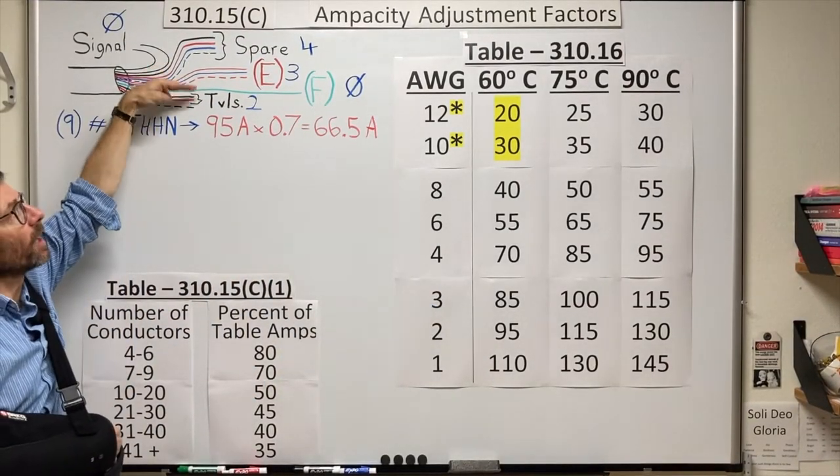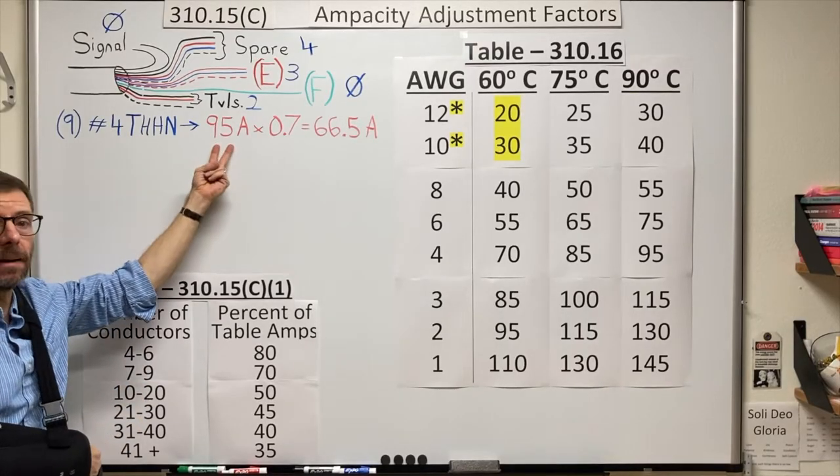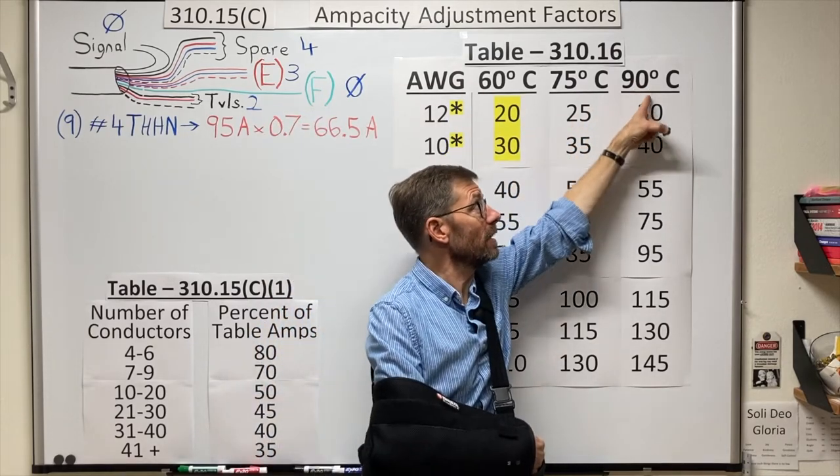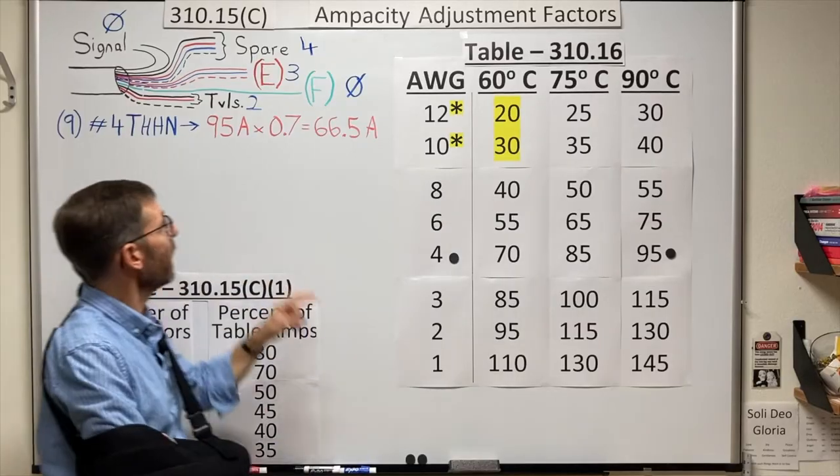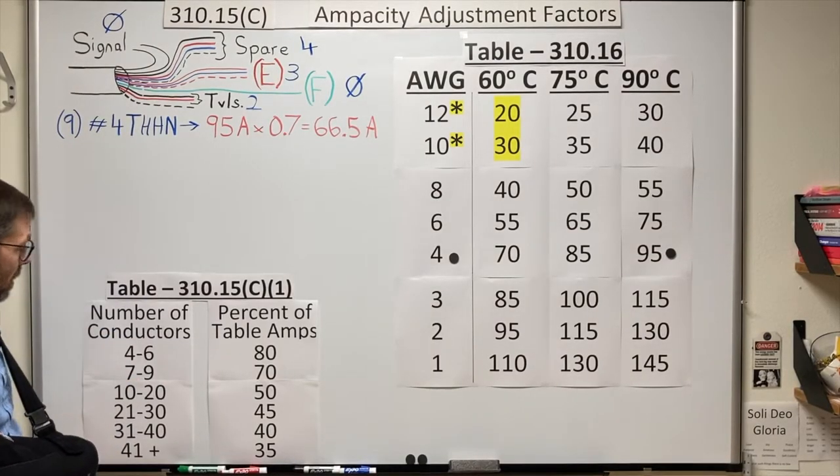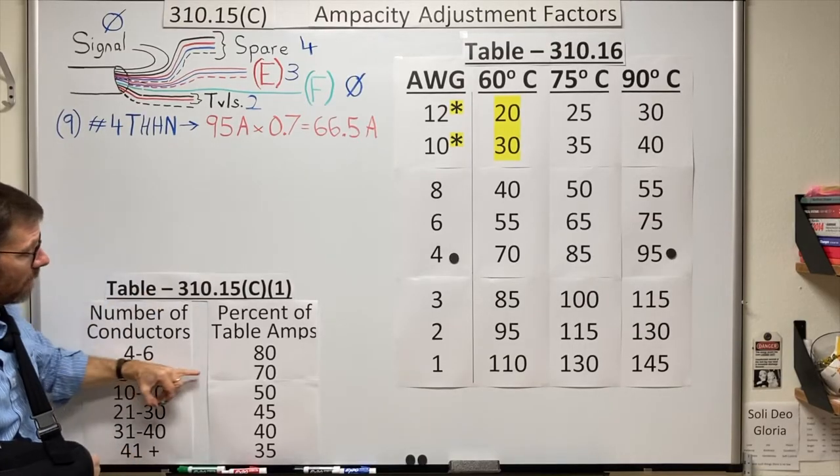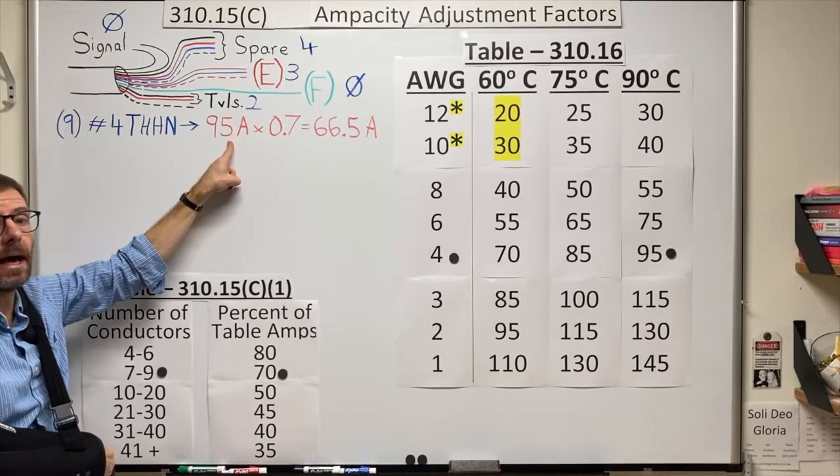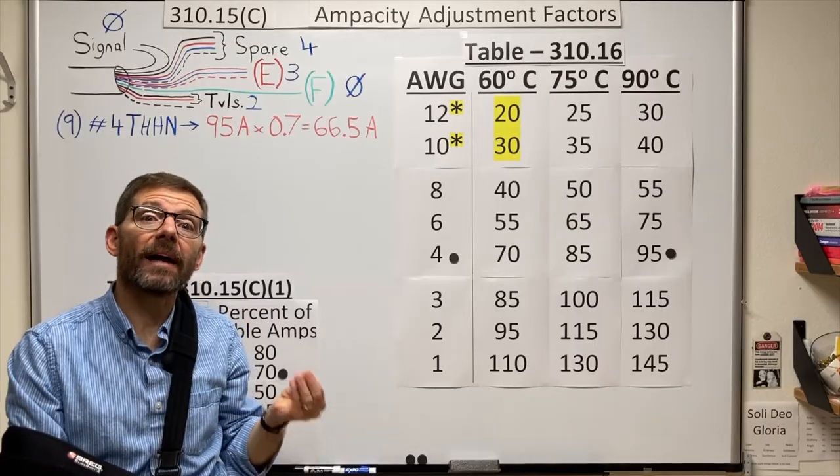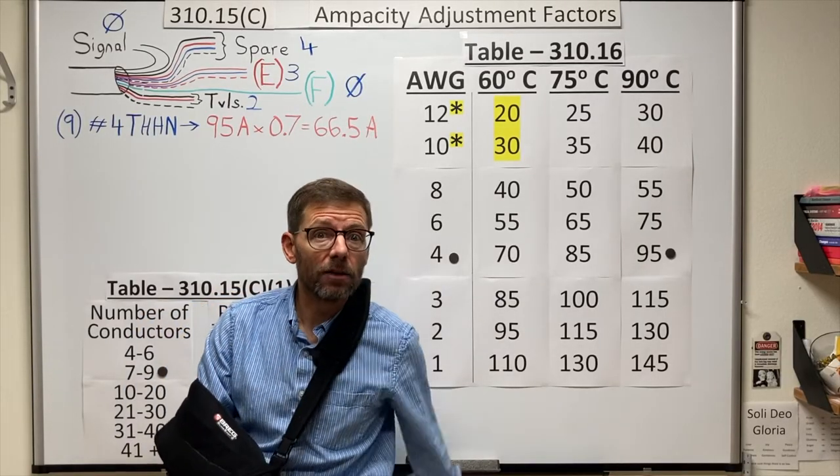Let's start by assuming all these wires are the same size. If they're all number four THHNs, the basic process is to take the conductor's initial ampacity from my ampacity tables. The number four wire, THHN being a 90 degrees Celsius insulation, is good for 95 amps. But because my conditions of use have changed, I now have nine current carrying conductors. I need to use this table here, and each of these conductors is now limited to 70 percent or 0.7 of their original ampacity. Giving a new ampacity of 66.5 amps for each of those conductors. That's their max load under these conditions of use. And those conductors would need to be protected accordingly by the rules back in 240.4.